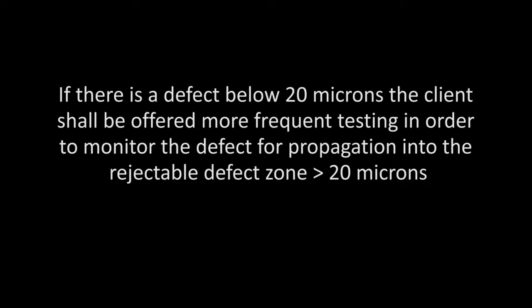The criteria for determining if a heat exchanger has failed the Gappscan test is minimum test pressure of 3 bar not achieved, possibly due to poor seals. Consistent flow during test period showing defect diameter more than 20 microns. If there is a defect below 20 microns, the client shall be offered more frequent testing in order to monitor the defect for propagation into the rejectable defect zone more than 20 microns.